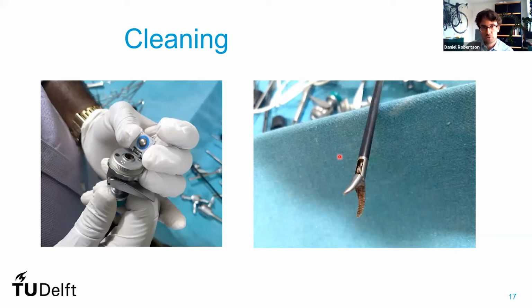And the other example is here, which is the tip of an instrument. Now, you see that the teeth of this instrument have become completely brown. And this browning is caused by the fixing of proteins by the disinfectants used. So disinfectants like Cidex or glutaraldehyde will fix the proteins onto these complex surfaces and make it more difficult to disinfect and sterilize every time. Now, ideally, an instrument like this should just have a clean, only metallic color. So this brown color, which is on there now, shouldn't be there.